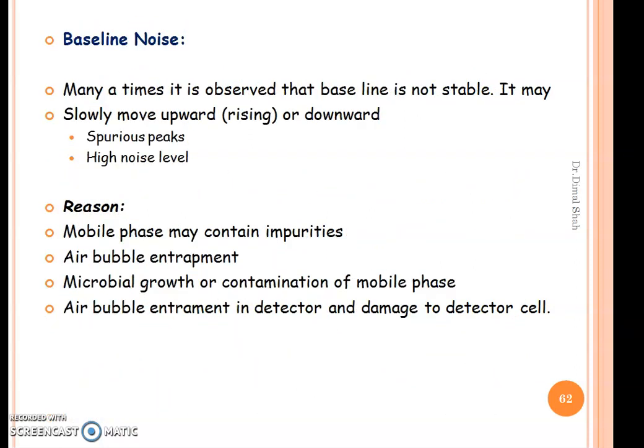Baseline noise. Many a time we observe that our baseline is not stable even after a sufficient period of time, after 20 minutes or 30 minutes. It may slowly move upward, that is rising, or it may move downward. There are chances of spurious peaks, that is unwanted peaks, or there are chances of a high noise level.